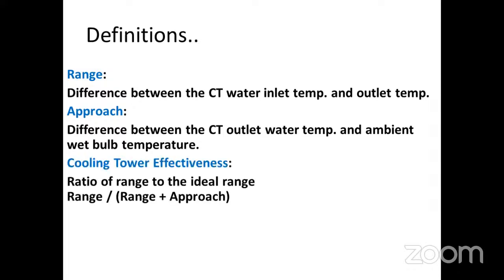Cooling tower effectiveness. Cooling tower effectiveness is the ratio of range by range plus approach. What is that range? Range we saw, it is the difference between cooling water inlet temperature, that is, cooling tower inlet temperature, that will be hot, that is coming out from the condenser, which is made to fall over the fill. That is cooling water inlet temperature. What is the outlet temperature? It is the cooling water outlet temperature that is in the bottom of the cooling tower. That is cooling water basin, we call it.